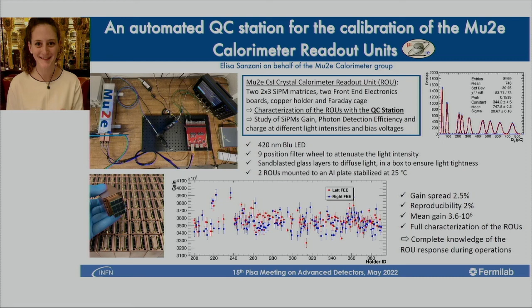And next is the automated quality control station for the calibration of the Mu2E calorimeter readout unit. This calorimeter uses cesium iodide, about 700 crystals, and this is read out by silicon PMs. This test station can monitor the silicon PM gain, photon detection efficiency, and charge at different light intensities and bias voltages. During this operation, stable operation can be checked.